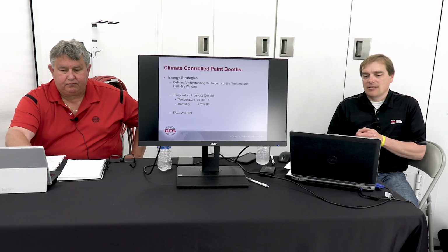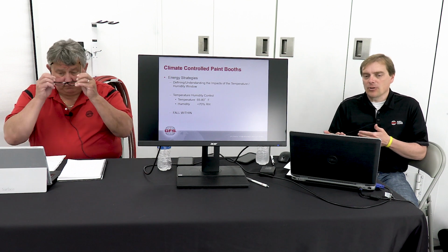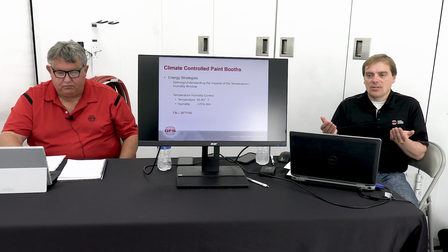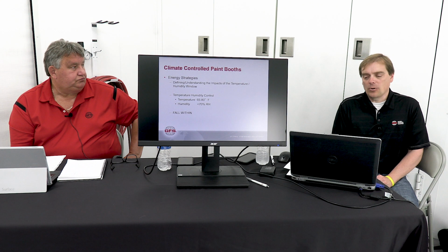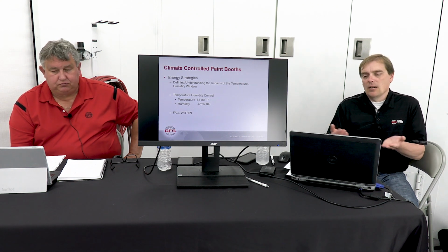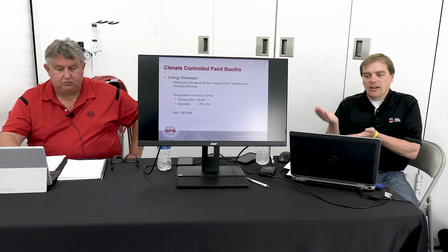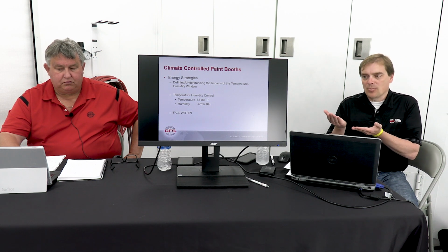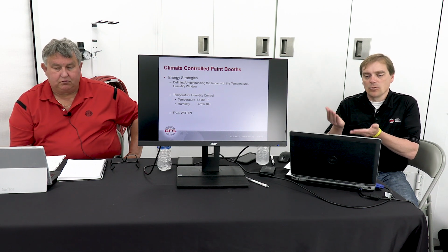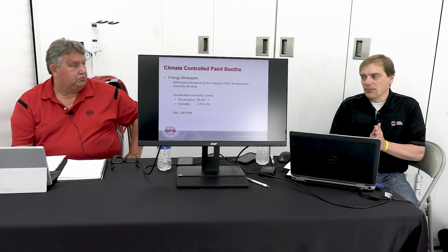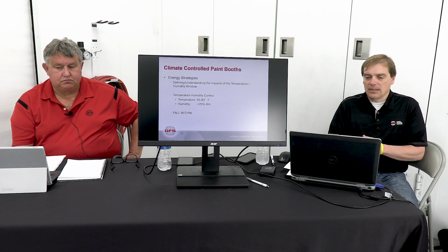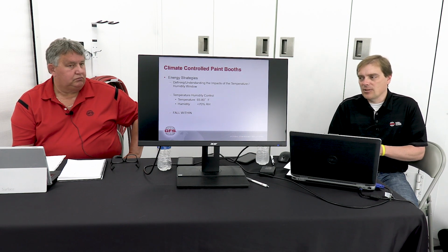window. And you can take that to the next level with humidity. Humidity works the same way. If there is a specific range that you're looking for, that your process requires, for instance, maybe it's 40 to 70% relative humidity, again, we would size our humidifying equipment to get to 40% on the driest, coolest day that you have. And vice versa, on the most humid day of the year, we would design that cooling and dehumidification system to get you below 70%.